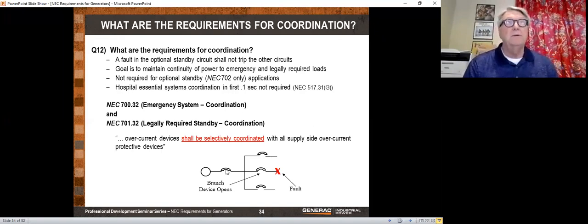Now, LSI circuit breakers, I generally don't want to use LSI circuit breakers because they cost a lot of money. You get an 800 amp circuit breaker, it can almost be the price of a car. It's just ridiculous. Biggest scam in the electrical industry, in my opinion, is molded case circuit breakers. And so I don't want to buy LSI because for the additional price of an LSI, I could have gotten a sound attenuated enclosure. However, if it's an emergency or a legally required system, sometimes you have to have the LSI in order to coordinate. And you don't want to try to do that after the generator is already on site. It's going to be much more expensive. So sometimes LSI makes sense if you have to have it for emergency or legally required systems.